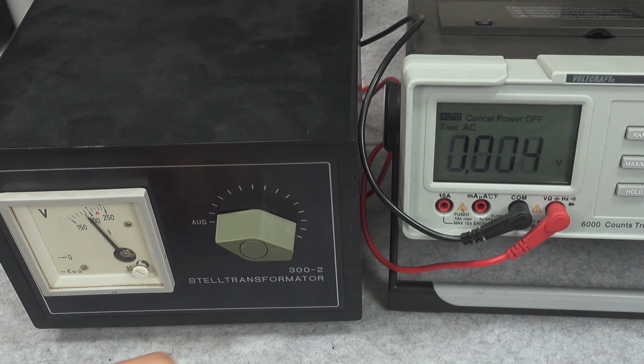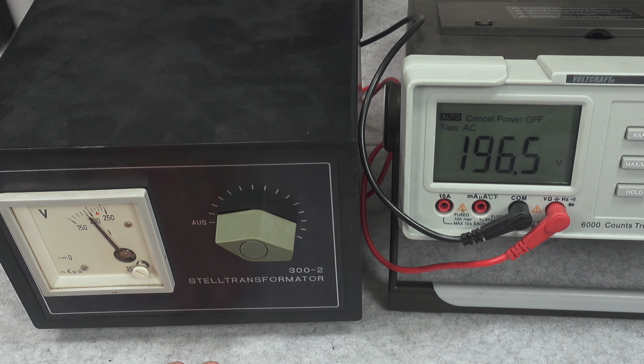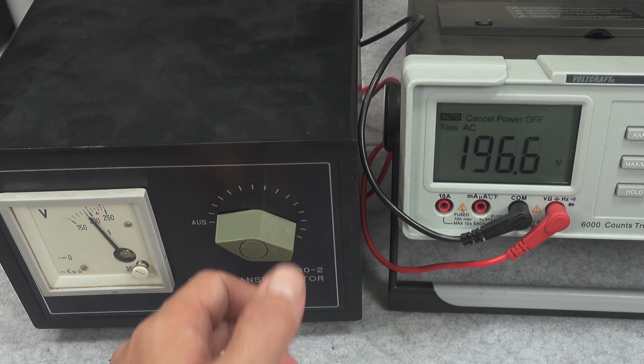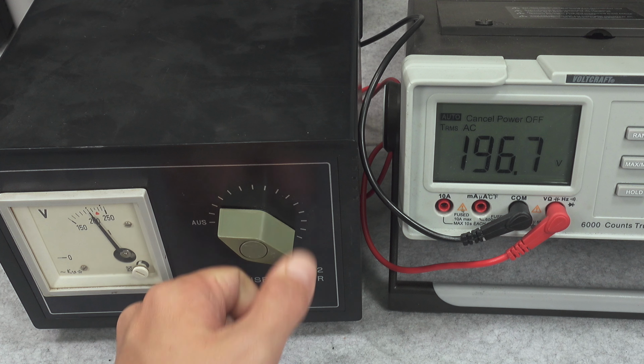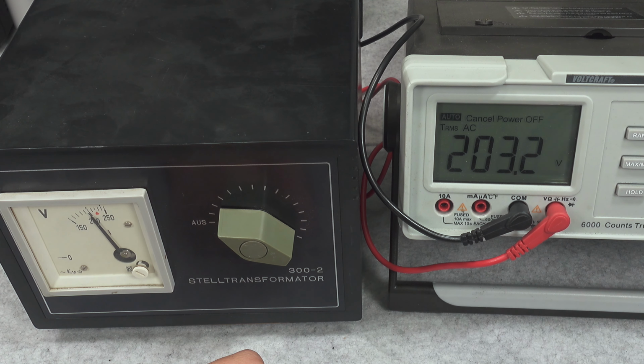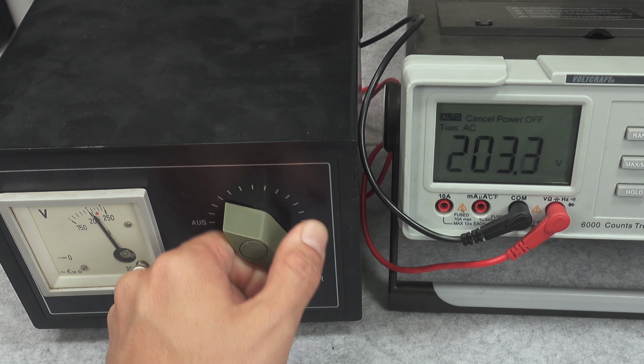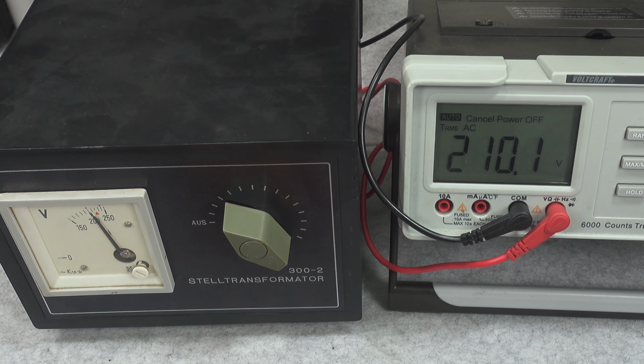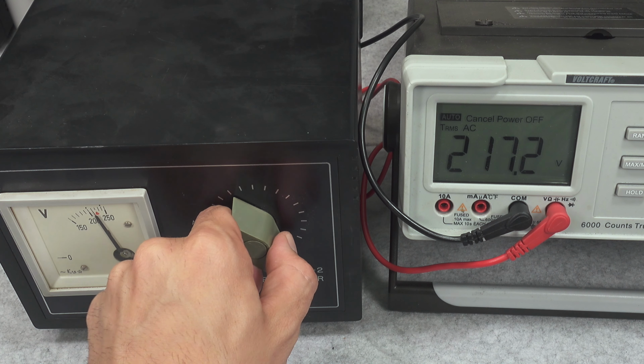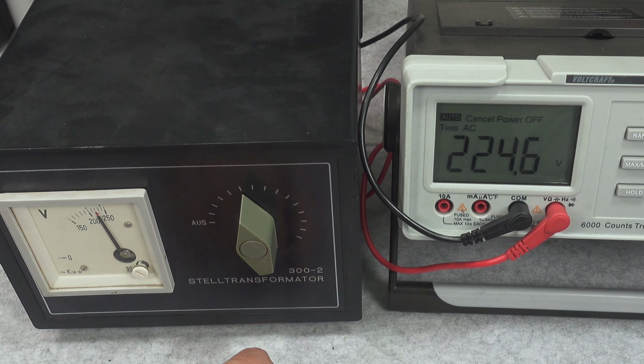So we go into our first step, we can see our voltage here, and as you can see on the measurement, we are reading 196 volts. So actually we dropped our voltage from the 219, and now we can slowly go and change our voltage. So as you can see, we've got 200 volts, then we've got another click, we've got 210, 217, and we go on so, just like that.